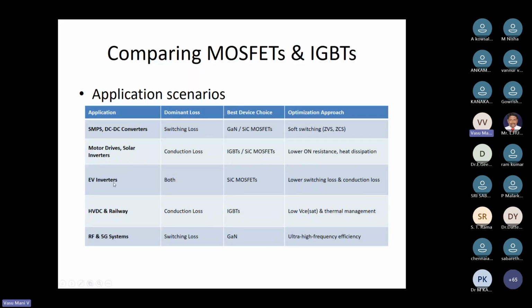The same applies to EV inverters, and HVDC and railway applications which work in the megawatt range. For megawatt applications, these SiC MOSFETs and normal MOSFETs are not available in the market. MOSFETs are available for 100 ampere, 200 ampere only, while IGBTs are available for 1000 ampere, 2000 ampere. So for high power applications, we need to consider IGBTs.